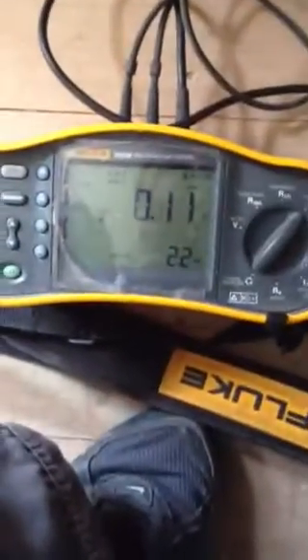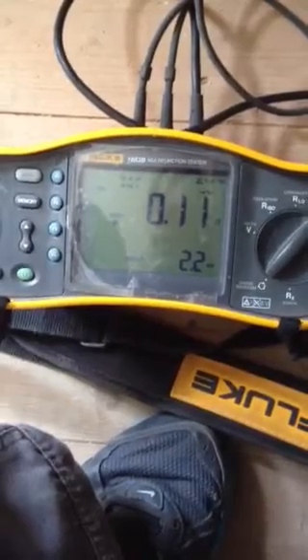So we need to connect one of the test leads onto the earth, a good connection, and we're going to put our probes onto the top of the main switch, which is obviously the live part of the main switch. I'll try and get a good camera view for you. Neutral first, and then onto live, and then press the test button. Okay, and we have an earth fault loop impedance of 0.11 of an ohm.